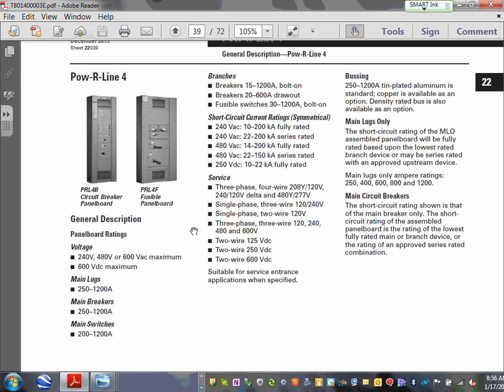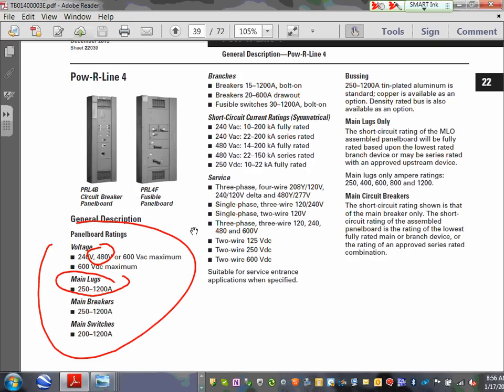I can't emphasize enough, when I ask you guys for cut sheets and you say, Adam, here are your cut sheets ready, always pay attention when you're dealing with a cut sheet. This is probably the most important thing in the cut sheets. So if the voltage is 480 up, here's my 480. What's the amps? Look at the amps. Main lugs only, it gives you all these ranges. Main circuit breaker, all your ranges. So if my panel is 480 and I need a 600 amp circuit breaker, here you go. Is it within that range? Yep. Main lugs or circuit breaker. Here's your panel.